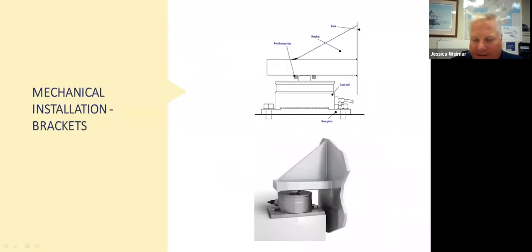You'll see that one that we looked at where the tank was sitting down through the mezzanine. This would be an example of where that leg came off the side of the tank, and there's nothing more than a centering ring sitting on top of our load cell. That's all you need. You don't need to have any other way to stabilize the load cell.